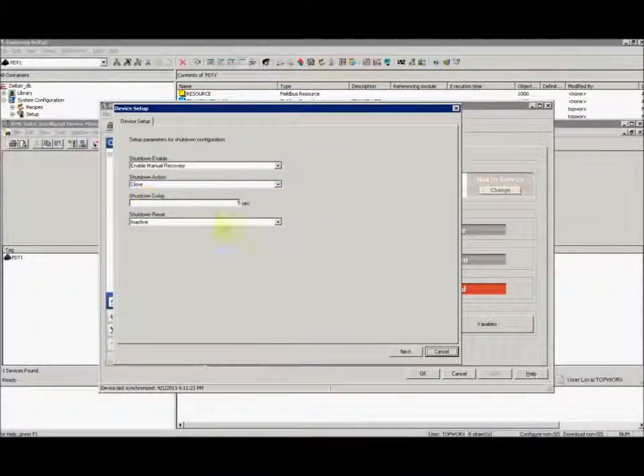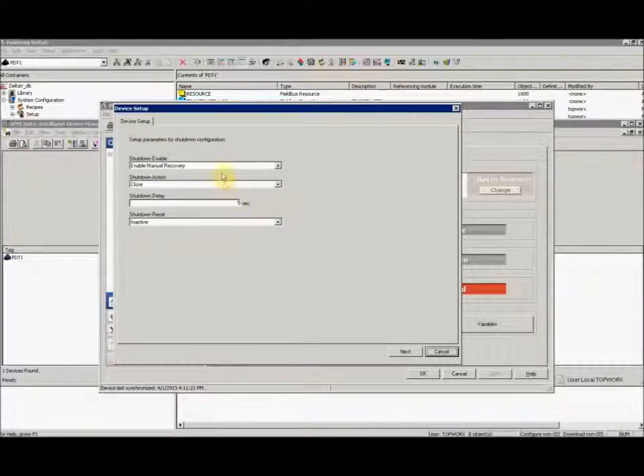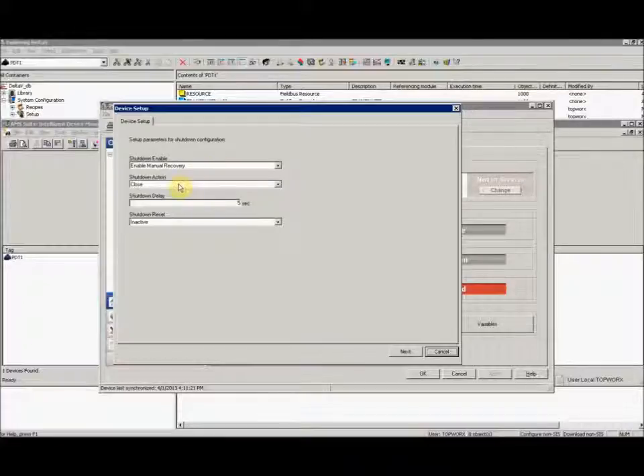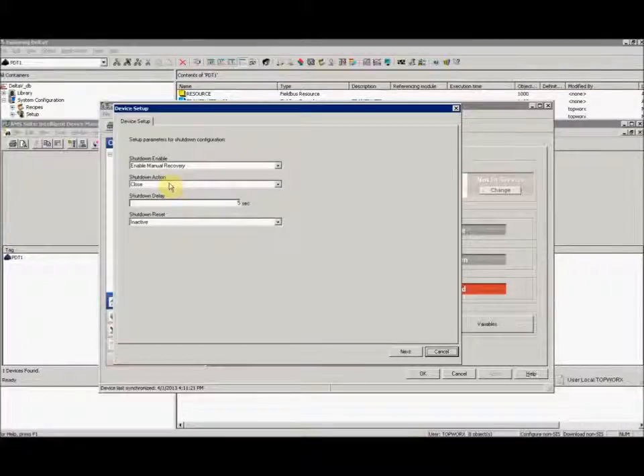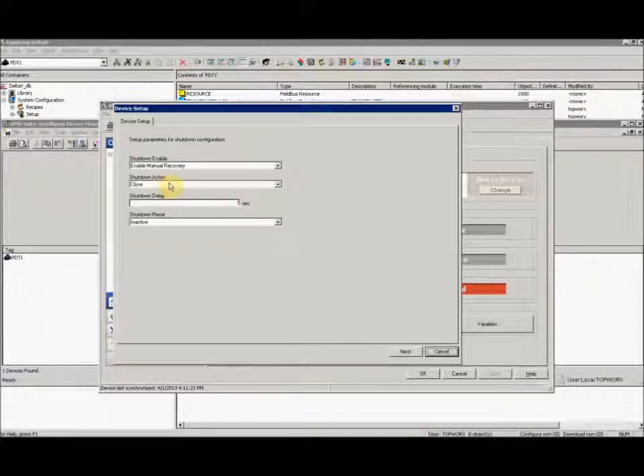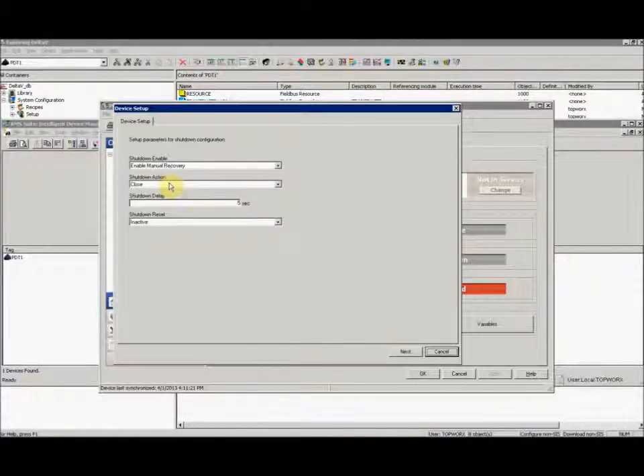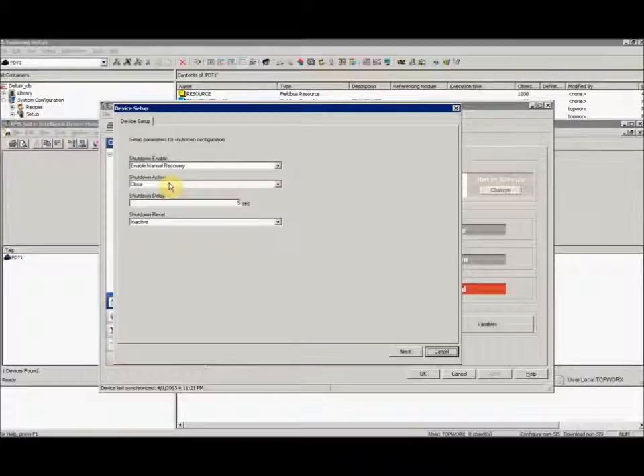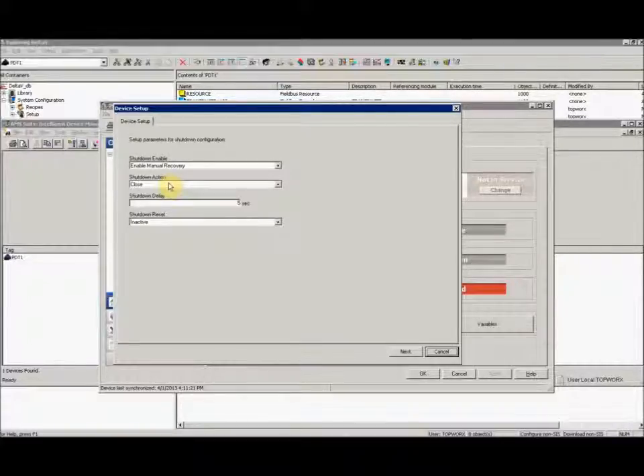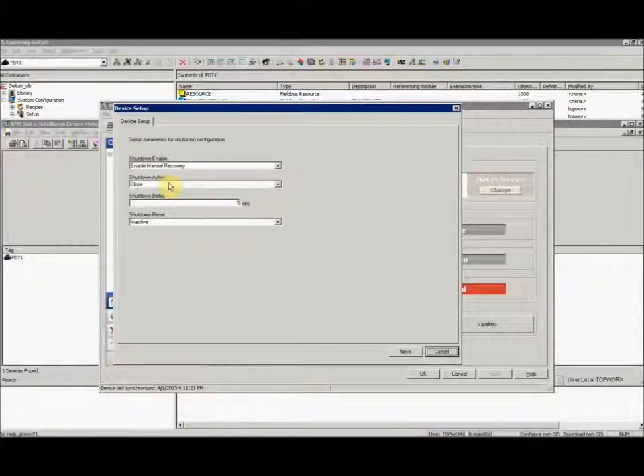This next window is shutdown configuration. Inside the sealed cube, there are two circuit boards, a sensor board and a foundation field bus board, and they are linked by a physical connection. If the cube senses any fault in the integrity of this connection, either electrically or physically, it will enter into this shutdown mode if it's enabled.